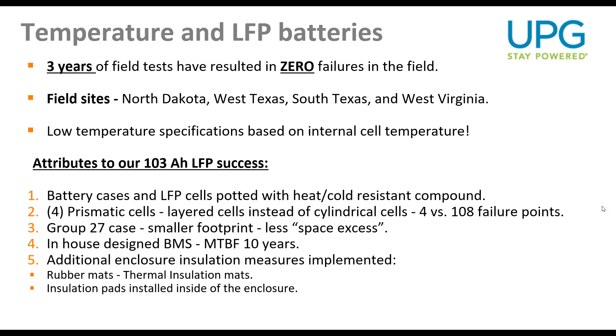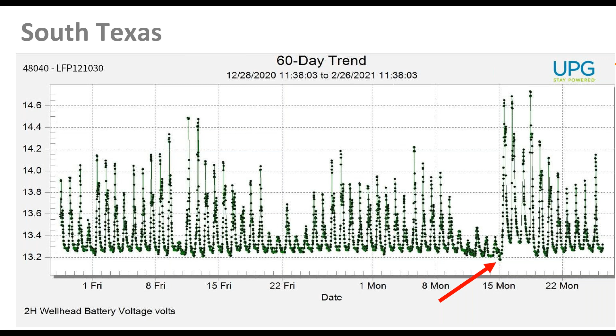As they say, the proof is in the pudding. We have 60-day trends from the field, from December 28, 2020 through February 26, 2021. This particular graph is from South Texas. We had a huge cold front come through Texas during the time frame marked by the red arrow, and you can see the lows of the voltage at night when the battery is discharging, where the voltage stays at 13.2, and the spikes are when the panel is working and the battery is charging to full. What's impressive is the balance and stability of how a lithium iron phosphate battery runs in the field.